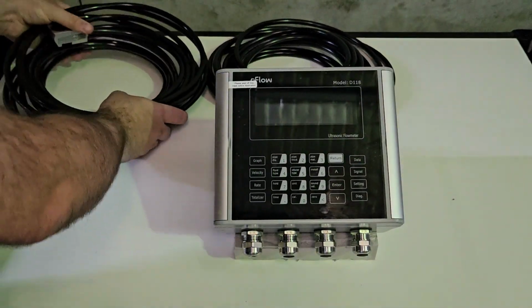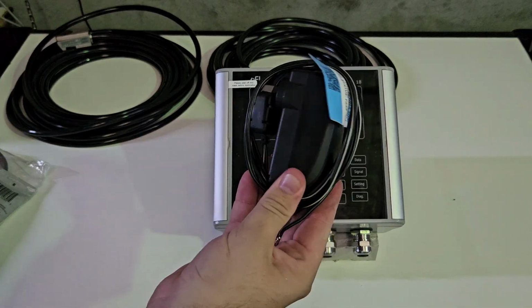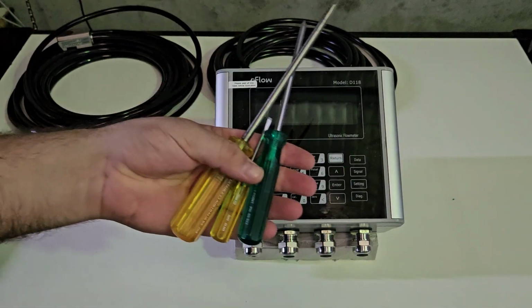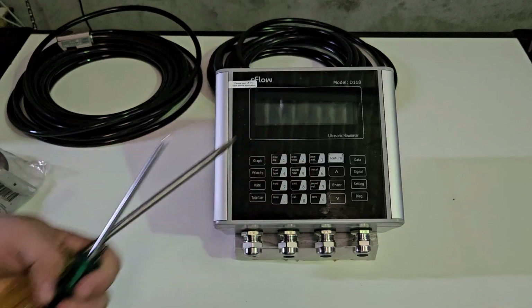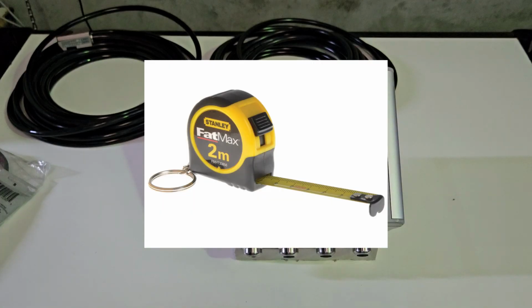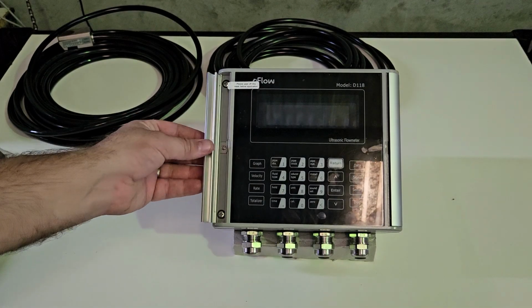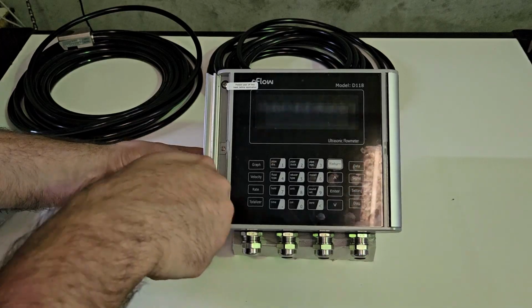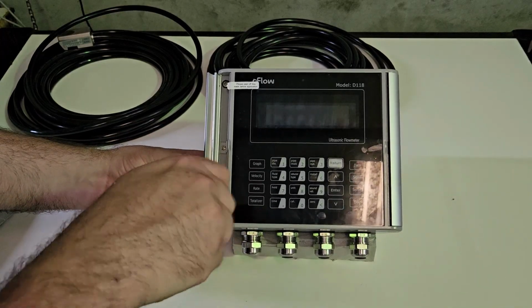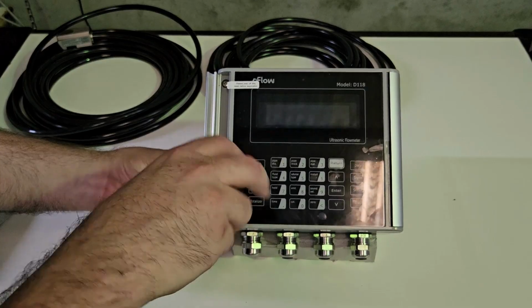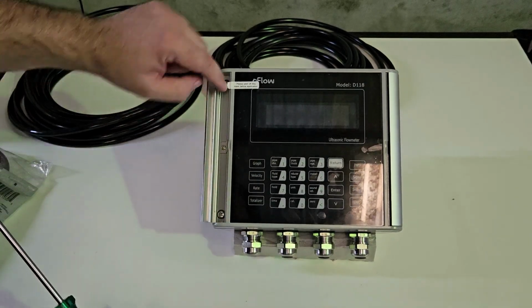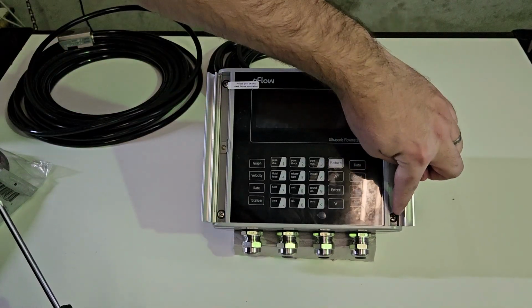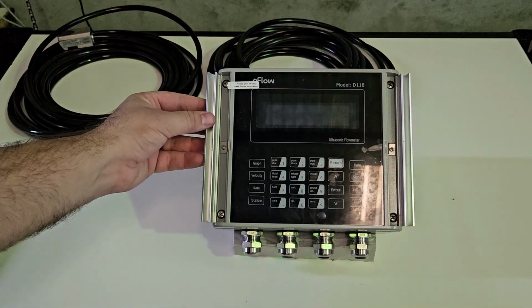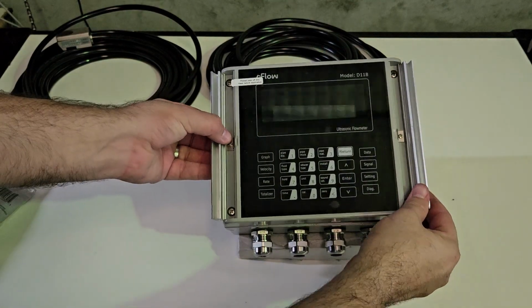Some other things you will need for the install include a 12 to 36 volt DC power supply, various size screwdrivers, and a tape measure. To begin the install, first open the left and right screw covers and unscrew all 4 of the corner screws. We have pointed out each of the screws which you should loosen. Now open the flow meter. It hinges on the left side.